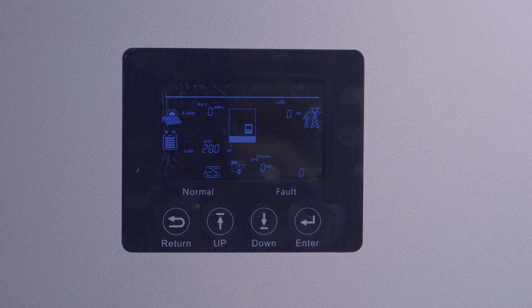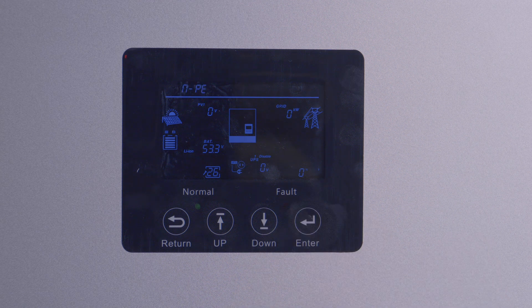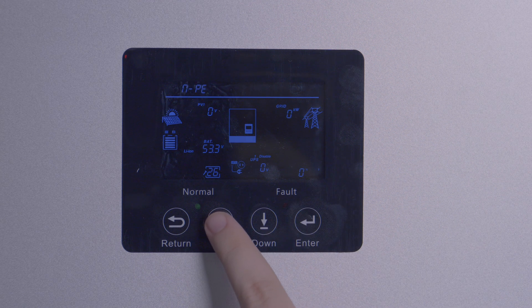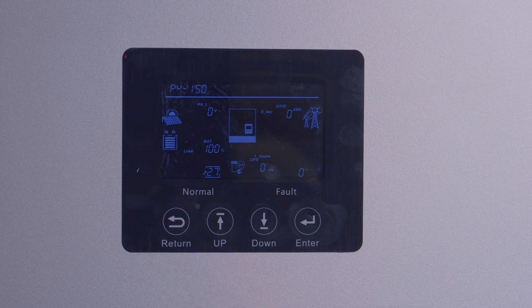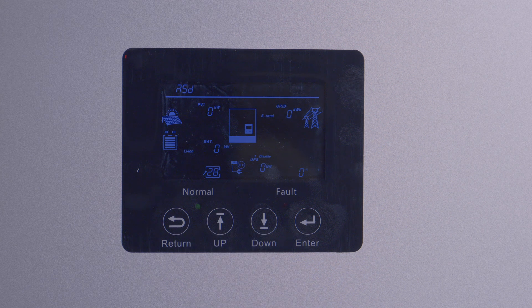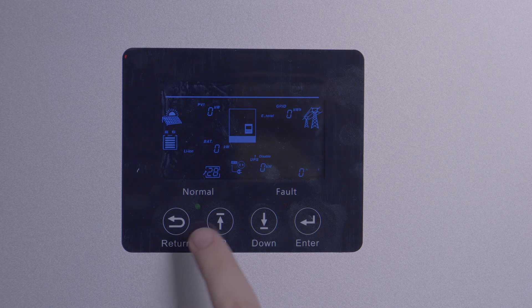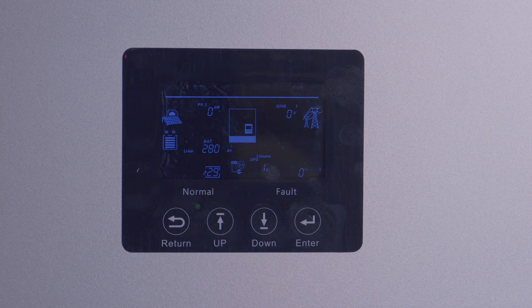Setting twenty-six is neutral ground bond. This is the static enable/disable function, where enable will allow the inverter to form the bond and disable removes that bond. Setting twenty-seven is PV isolation protection — it's disabled by default, as most systems will use MLPEs on the array for code compliance. Setting twenty-eight enables or disables the RSD terminals on the board, which is enabled by default and should be wired to an external shutdown button for safety and code compliance. Setting twenty-nine is the AFCI protection, which is enabled by default and recommended to leave enabled.